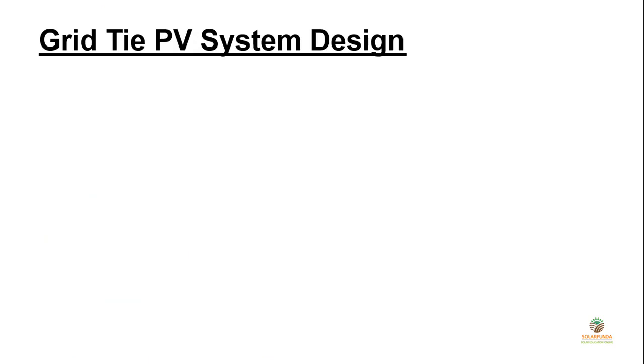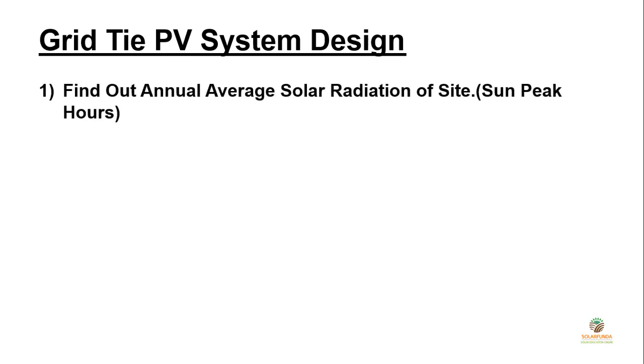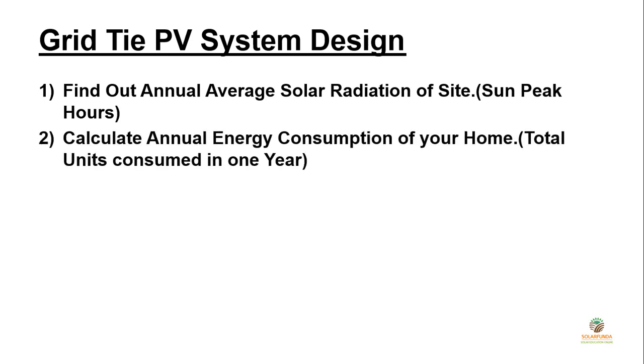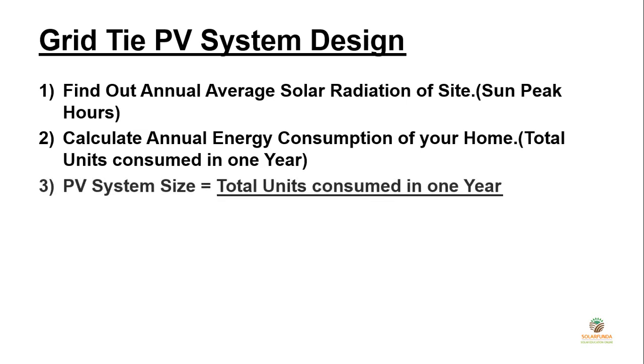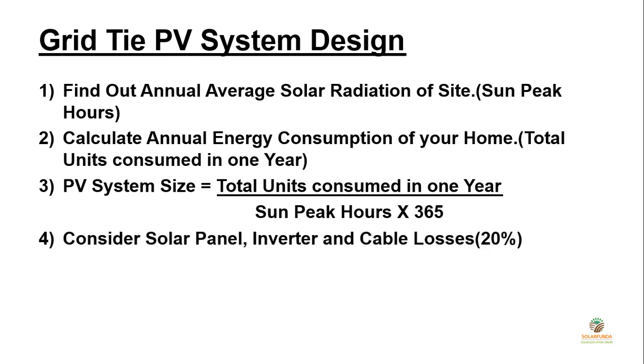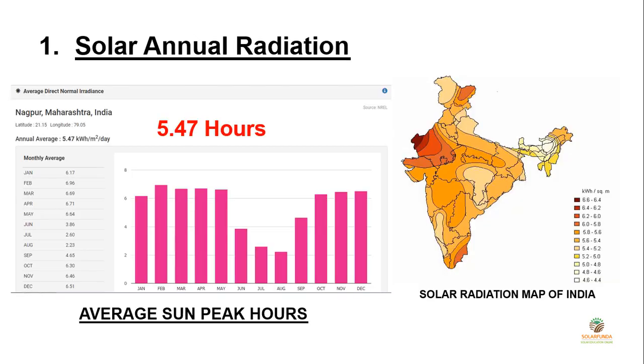Now we will learn how to design a grid-tie PV system. If you want to know how much kilowatt of PV solar system you need, follow these steps: First, find out the annual average solar radiation of your location — that equals the sun peak hours. Then calculate the annual energy consumption of your home — the total number of units consumed in one year. Then use the formula to find PV system size, consider losses in the PV system, and finally make a list of materials required for the solar project.